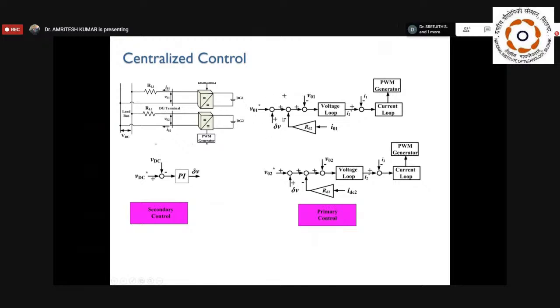Okay, so it means that because of these two, the voltage gets decreased. So now, to enhance the voltage in the DC link, the secondary control is giving information, based on the error and the controller, on how much voltage we need to add to enhance the common DC voltage to the reference value, the value that we targeted to achieve.